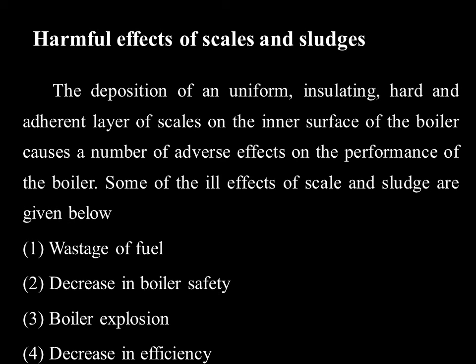And then decrease in the boiler safety. Decrease in the boiler safety means, if the fuel is used continuously and steam is forming continuously, and suddenly a particular part of the scale is dropped, that particular portion conducts the heat excessively and immediately. The water in that part converts very rapidly into the gaseous form and expands rapidly, and it will lead to boiler explosion. Thus, one thing is interlinked to another, and they lead to wastage of the fuel, decrease in boiler safety, boiler explosion, decrease in efficiency, etc.